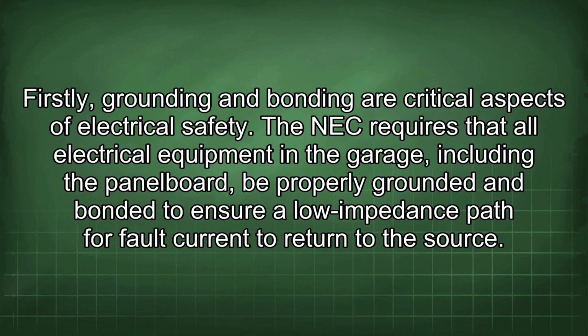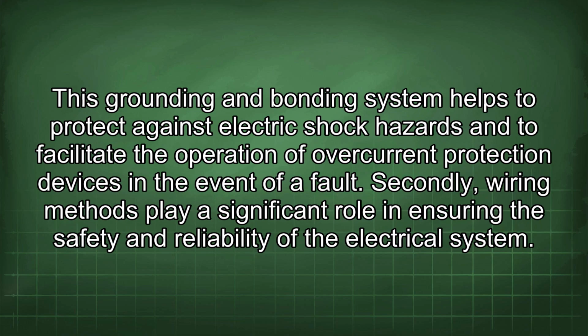Firstly, grounding and bonding are critical aspects of electrical safety. The NEC requires that all electrical equipment in the garage, including the panel board, be properly grounded and bonded to ensure a low impedance path for fault current to return to the source. This grounding and bonding system helps to protect against electric shock hazards and to facilitate the operation of overcurrent protection devices in the event of a fault.